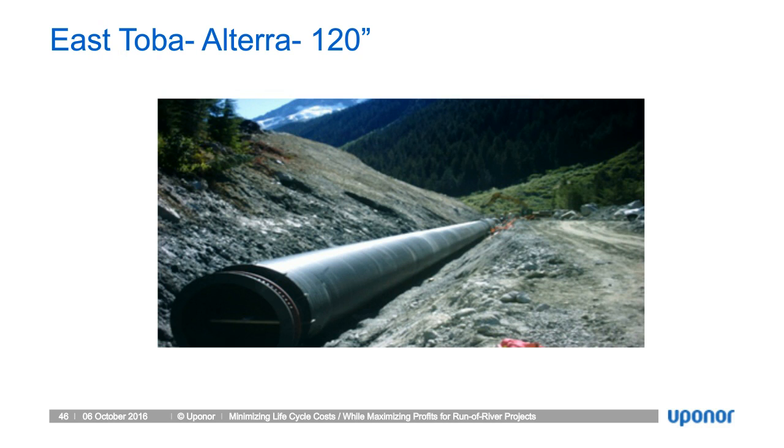They invited us to do a walkthrough, myself and Jerry Groen from engineering. Had to do a walkthrough with these folks in 2014, and the look of the pipe was just amazingly in great condition. We had no issues or anything to concern ourselves with. The deflection of the pipe was all to where it had to be, and they're generating the power that they were supposed to be producing, and they're very happy with the inspection. And the cost of doing that inspection was just our time to walk through, so very minimal maintenance cost on any of these projects.